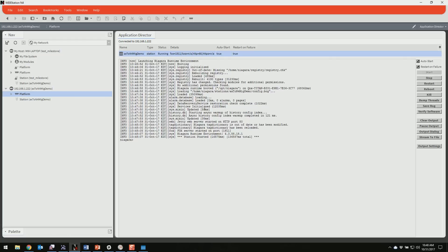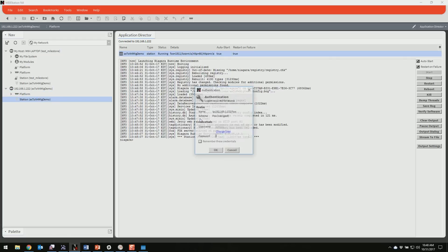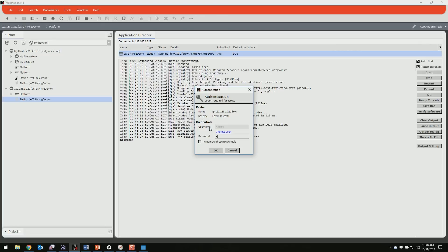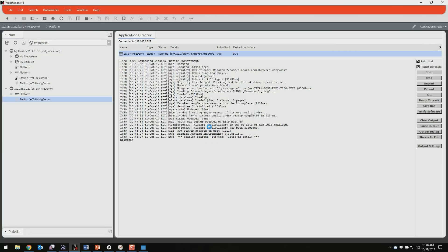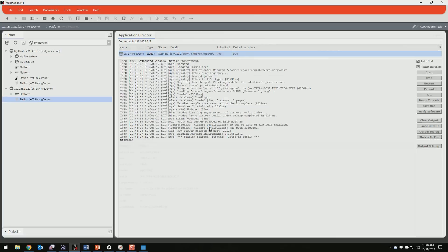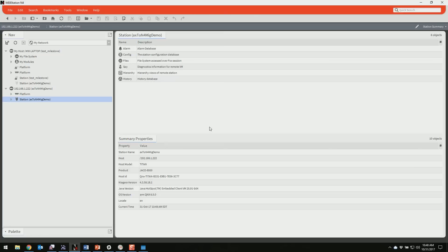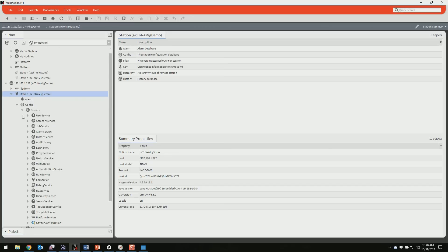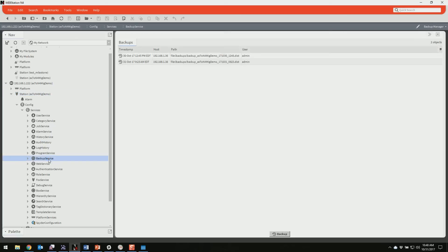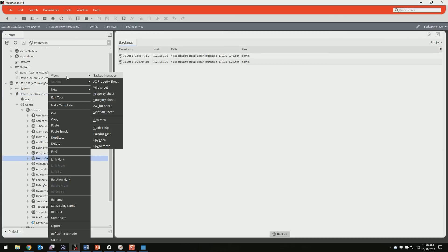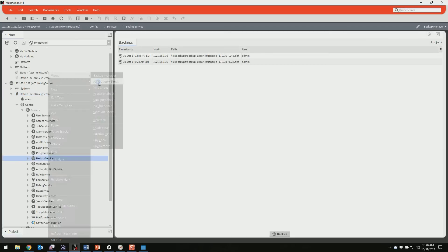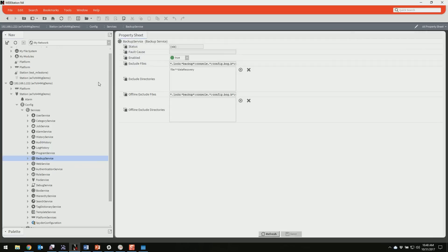Okay. So our station's up and running now. So I can log in. And we have one last change to make. So those exceptions that we got rid of so that we could have the alarms and histories brought into our backup, it's a good idea to add those back in because when you're making changes down the road, you don't want to have to be bringing in months worth of histories with your backups that you make once you're done for the day. So we go back into our backup service here.